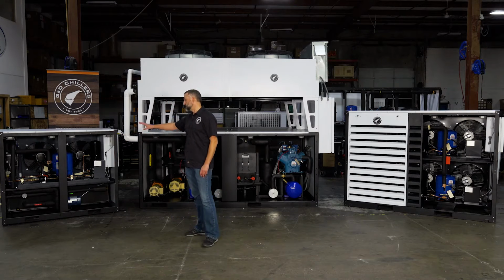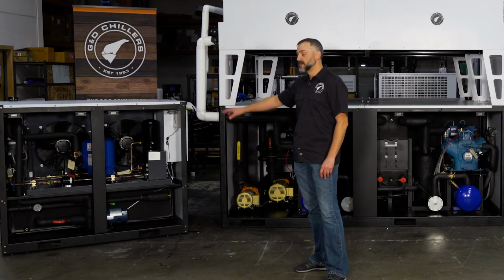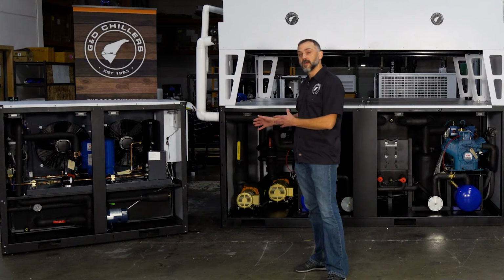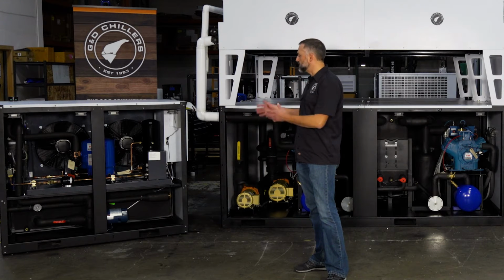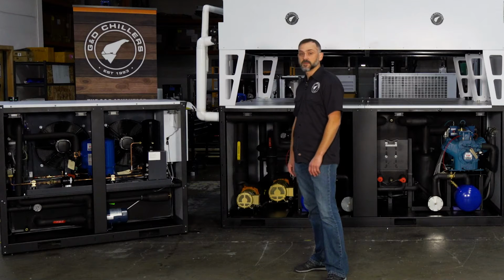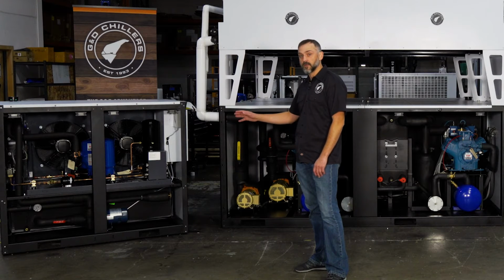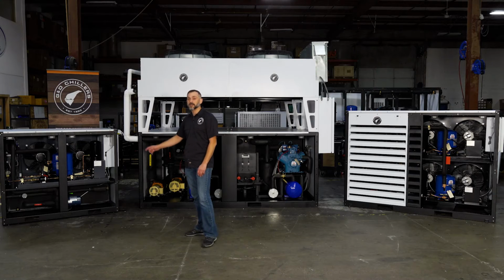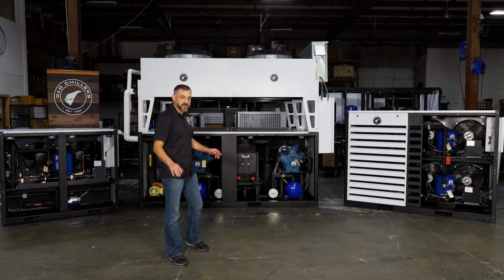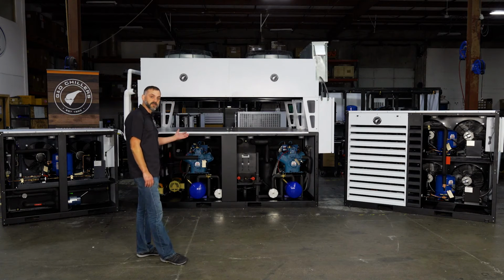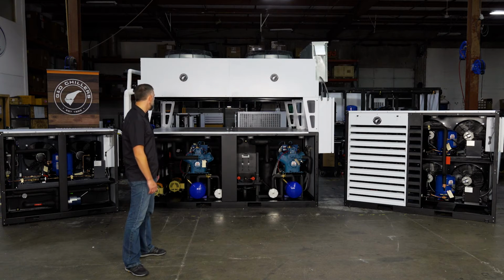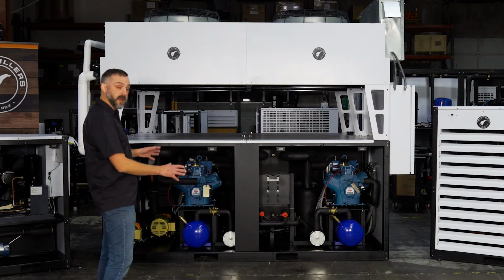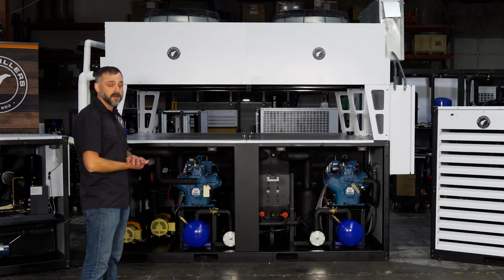This compressor is a fully hermetic sealed compressor. They're great for what they are. And they have served so many customers over the years very well. They're very hardy compressors, and they're awesome. We've had great luck with those compressors. We change though when we get to a larger production scale scenario. This chiller here is going to have 2 semi-hermetic reciprocating compressors. There's a lot of benefits to the 2.